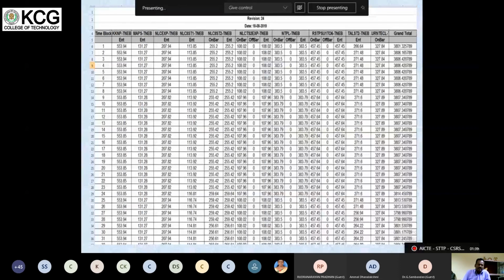For each 15 minutes, what I am going to generate, I will give to the centralized load dispatcher. What I am drawing for a day, 96 blocks, I am going to give. So like this, every 15 minutes, very cleverly, very brilliantly, very efficiently it is maintained. Otherwise, it is not possible to maintain the grid system. So we see that I am getting the voltage, I am getting the frequency, that's all. But how many people are working behind this? That is very difficult. You can think over how many people are working, how hard they are working, to maintain this frequency and the voltage in the grid system.